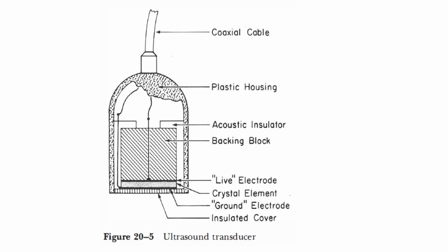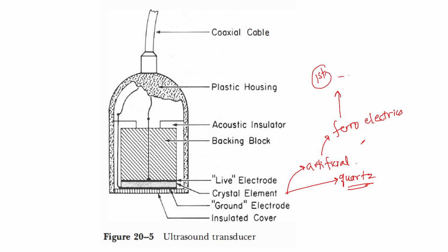This piezoelectric chemical or crystal element could be quartz. Some of the natural elements have this piezoelectric effect, like quartz, but most of the crystals which are used in our ultrasonography are actually man-made or artificial crystals. This group of artificial crystals which have the piezoelectric effect are called ferroelectrics. The first ferroelectric or first piezoelectric crystal is barium titanate, which is the first piezoelectric ceramic ferroelectric. Nowadays, barium titanate and others have been replaced by lead zirconate titanate.